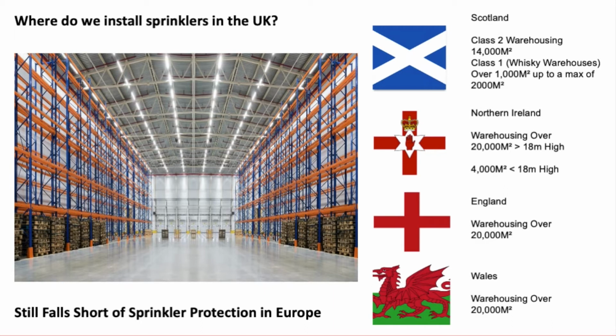I know it's been touched on already, but four areas of the UK have different building standards when it comes to installing sprinkler systems. In Scotland, Class 1 and Class 2 warehousing of 14,000 square metres and more has to have sprinklers installed. For Class 1, such as whisky warehouses, anything over 1,000 square metres up to a maximum of 2,000 has to have sprinklers installed.